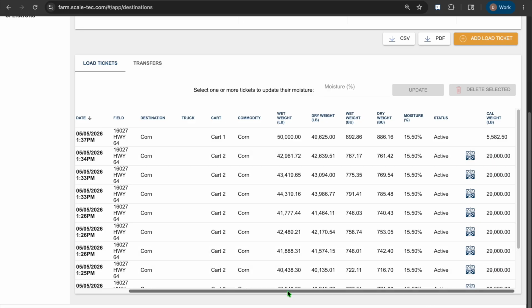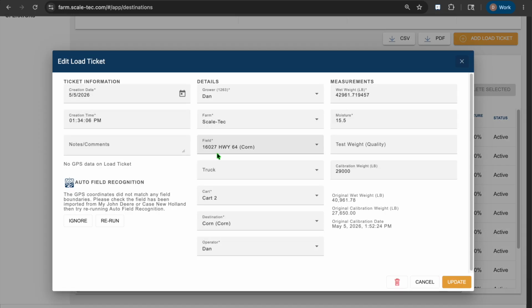If I open one of these loads, you'll notice REAP keeps a full record of the post-calibration. You can see the original weight, the original calibration, and when the correction was made. What would have taken hours of manual edits is now fixed in seconds, with complete traceability. Post-calibration gives you confidence in your data, even if your calibration wasn't perfect during harvest.